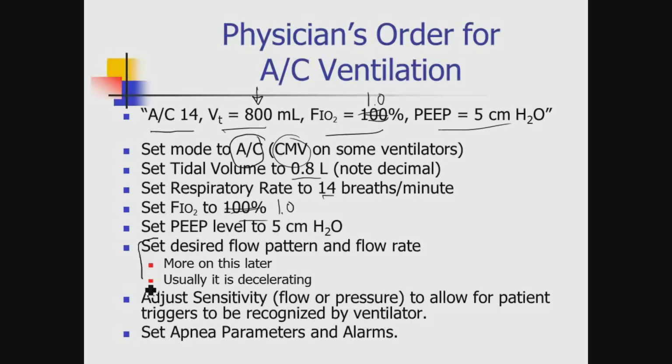In volume-based ventilation, we're going to go ahead and set a flow pattern and a peak flow rate. We'll talk about that later. Set my sensitivity to wherever I want. Set my apnea parameters. Once I got my patient hooked up, set my alarms. Your final evaluation will be this, only I won't give you these.